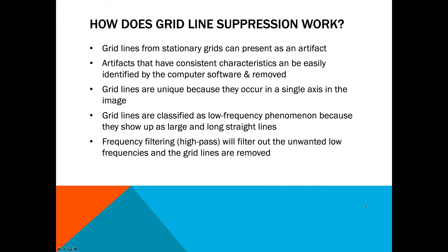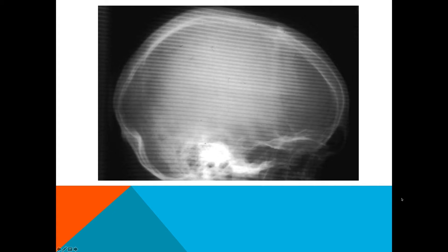Grid line suppression: grid lines from stationary grids can show up as an artifact, but this artifact has a consistent characteristic that's easily identified by the computer and can be easily removed. Grid lines are unique because they occur in a single axis and are classified as a low frequency phenomenon, showing up as large, long straight lines. High pass filtering will filter out the unwanted low frequencies and remove the grid lines. The final image shows what it would look like if the grid suppression software failed — you can see large grid lines — but fortunately we have software to take care of that. That's the end of this portion of the lecture.